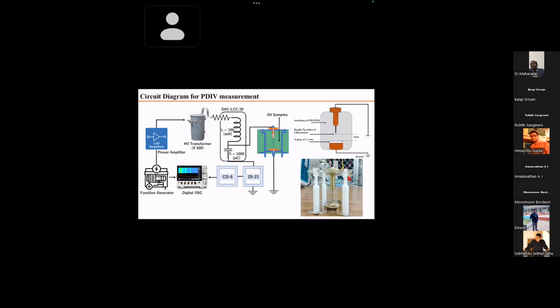I don't agree with that statement, because up to a certain temperature, as I said, maybe up to 50 degrees, which is the operating temperature of the transformer, less than that may be the normal operating range. But in an experimental stage, in the laboratory, if you go beyond that temperature, beyond 50 or 60 degrees, I don't think the breakdown voltage decreases the same way. It will be very different case to case. Maybe it will increase because of the chemical structure of the oil. Sometimes it's a paraffinic structure, and with temperature this paraffin structure may break.